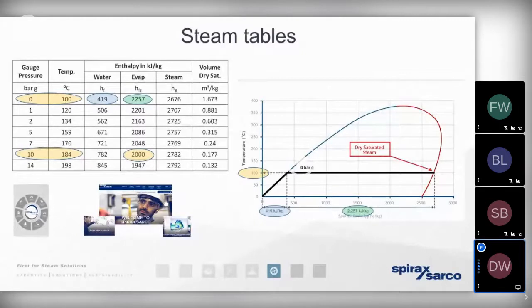But the first thing we want to do when we get that steam to the process is reduce the pressure. And we typically do this for 4 reasons. So first of all, it's for process control and efficiency. For example, if we're distributing steam at 10 bar gauge, 184 degrees, but the process only needs, let's say, 165 degrees, then any excess of pressure is going to be an excess of temperature. And that can be a problem with regards to not only efficiency, but also quality of the process.